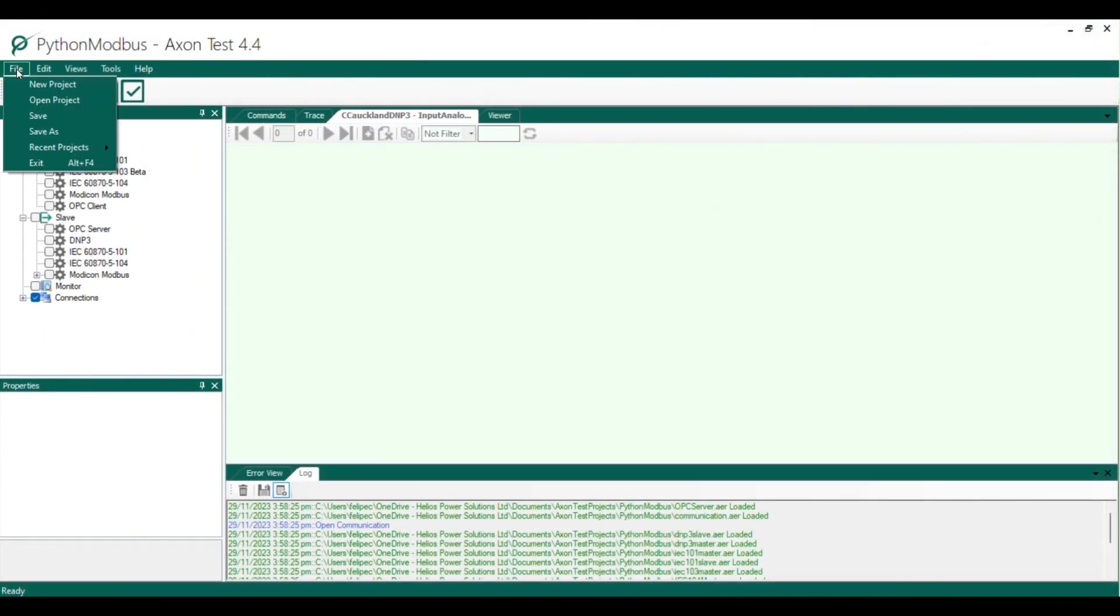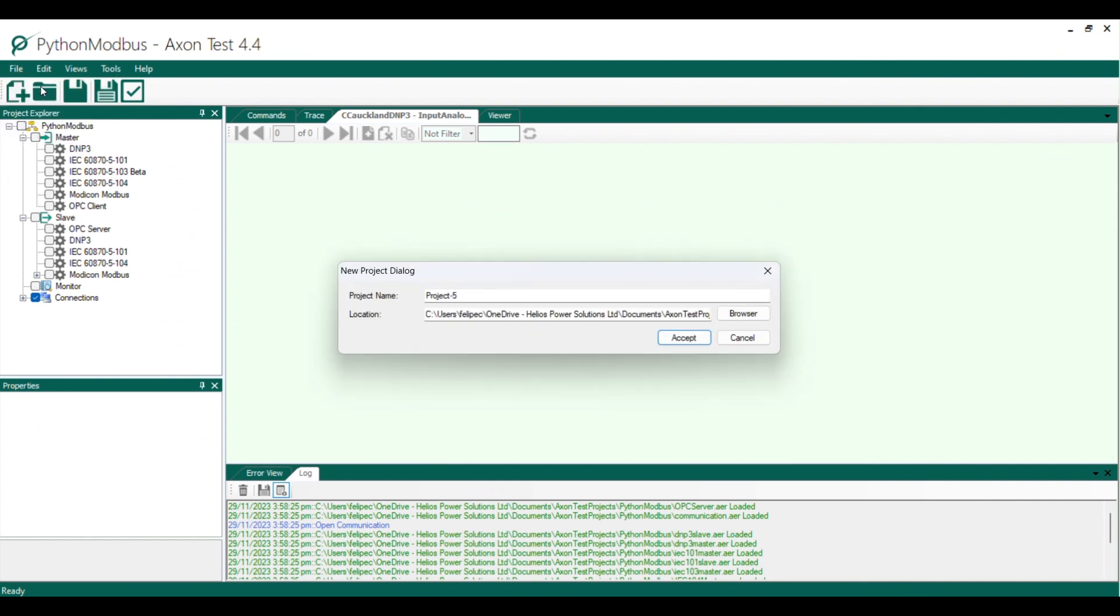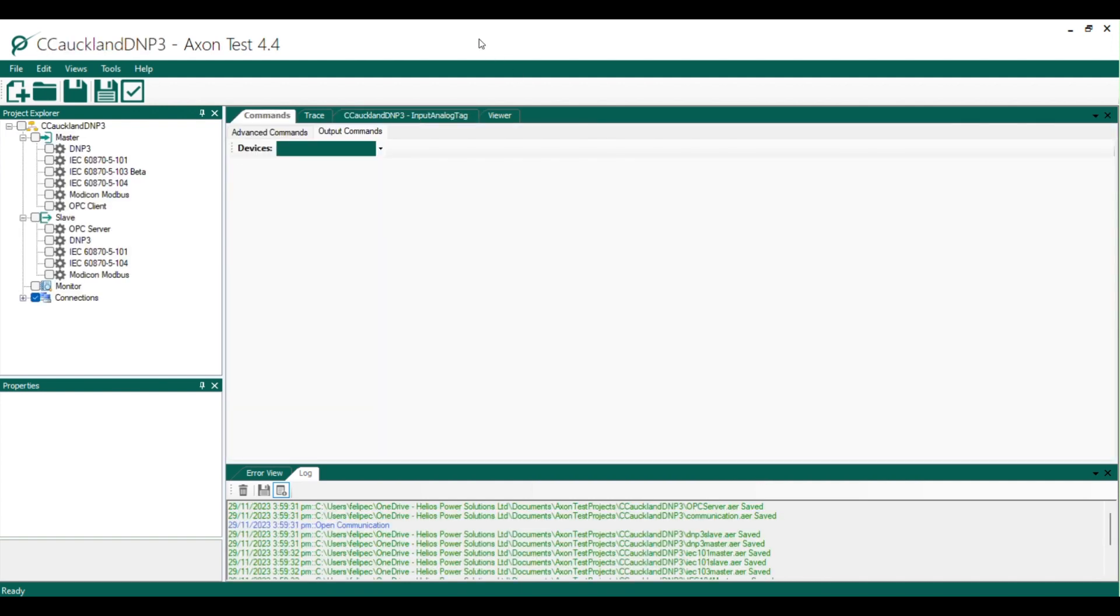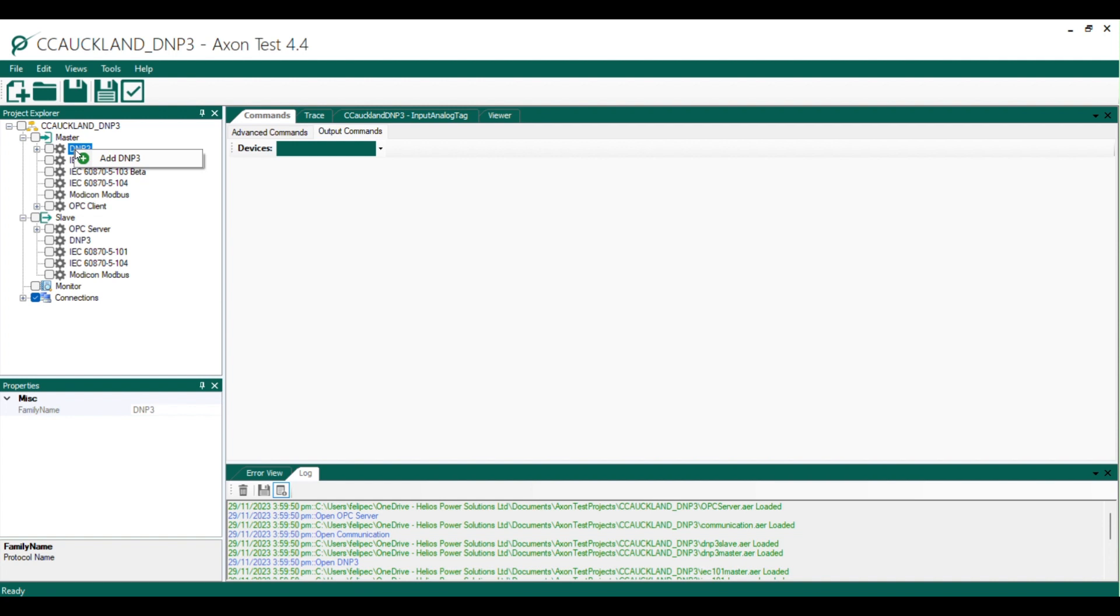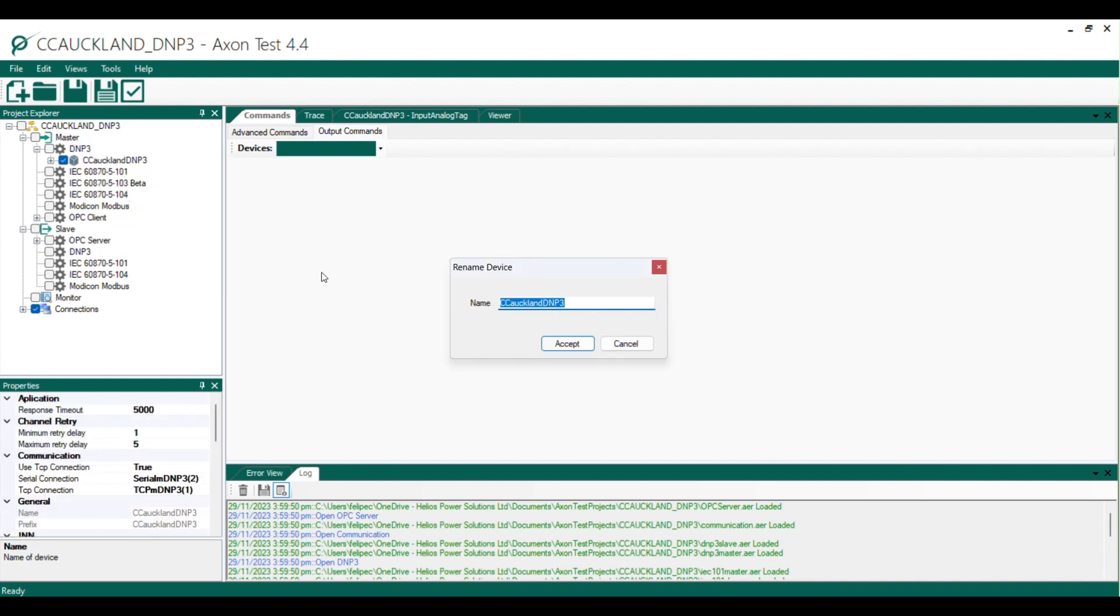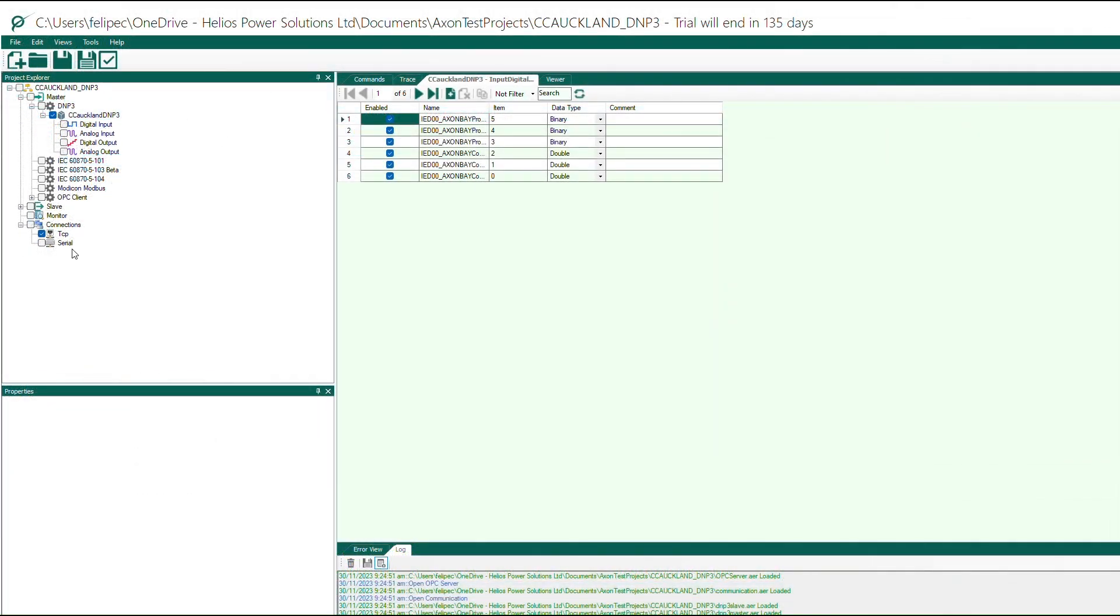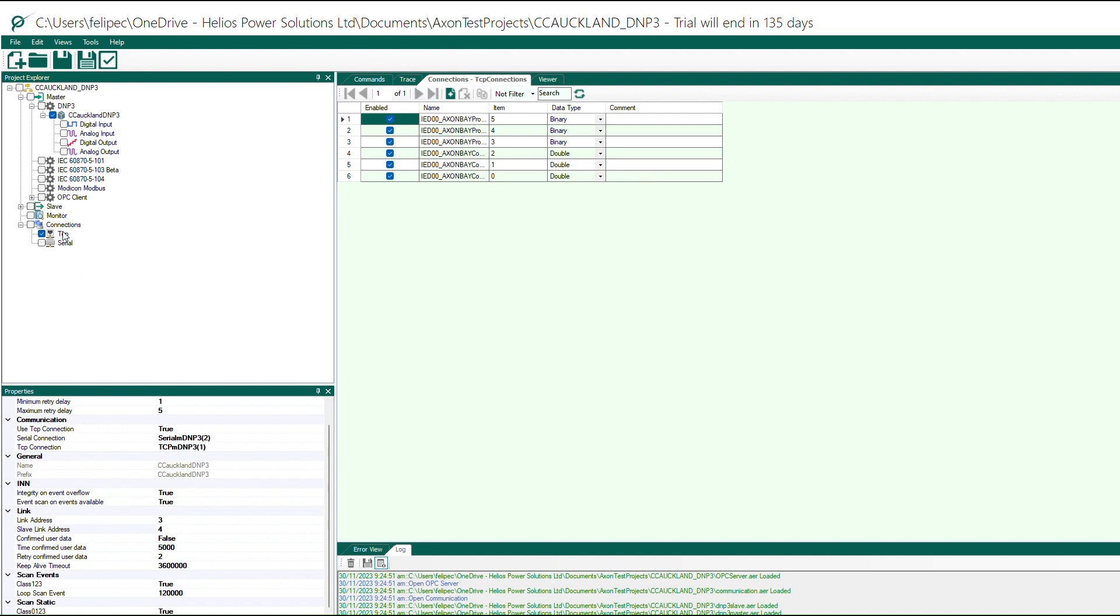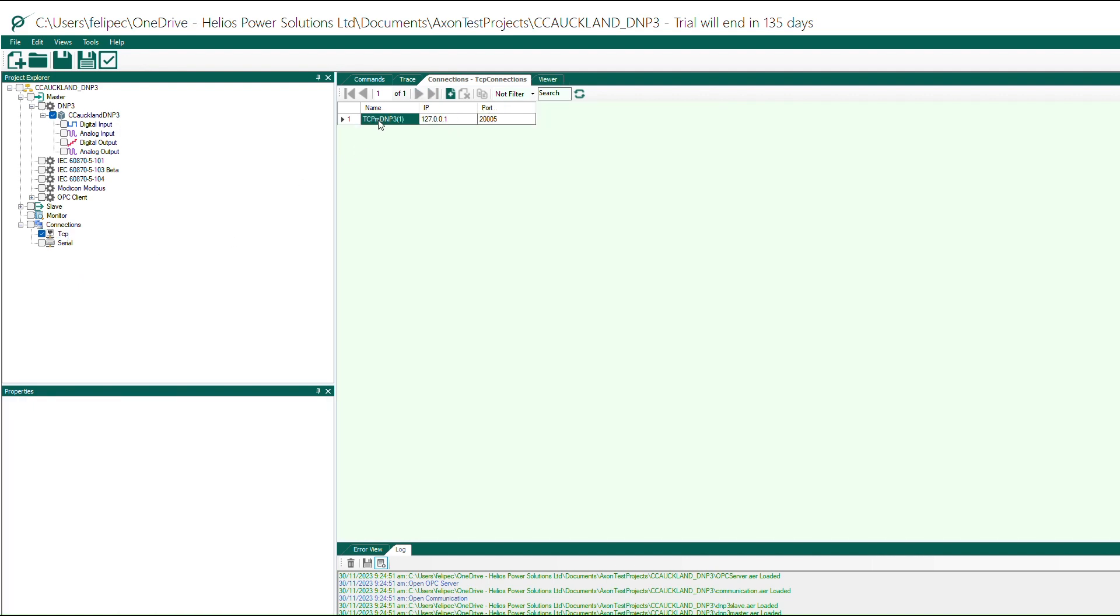At this moment we have prepared our slave DNP3. Next we need to create a new project in Axon Test and give it a name. In the project explorer zone you will create a new DNP3 master device. Afterward set up the communication parameters including the link address, slave link address, IP address and TCP port for the connection with your DNP3 slave.